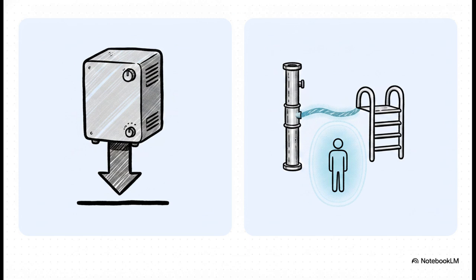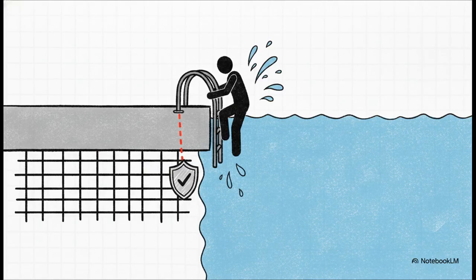By linking them with a bonding conductor, you ensure they are all sitting at the exact same electrical potential, or voltage. Think about it. If two metal objects are at the exact same voltage, current literally cannot flow between them. Bonding basically ensures you don't accidentally become a human conductor bridging two metal objects at different voltages. And let me be clear, this is not optional in high-risk zones. The standard strictly mandates bonding for conductive water piping, structural metal in showers, swimming pools, and even certain conductive building materials. I mean, think about the extreme danger here.